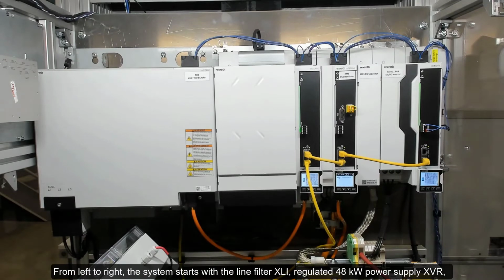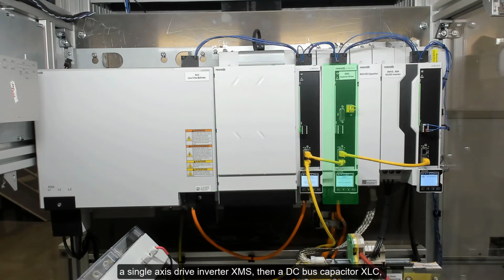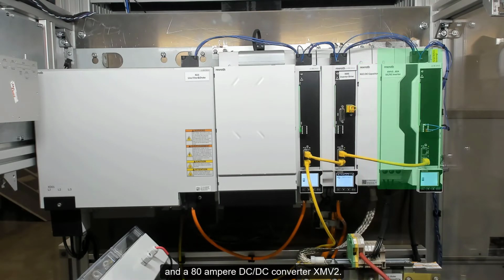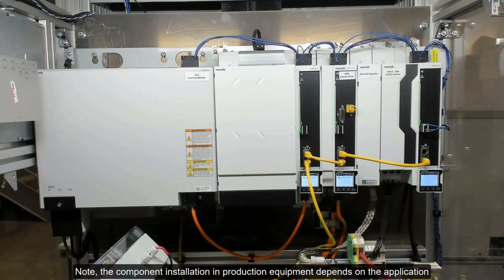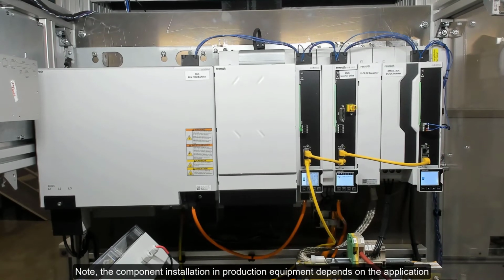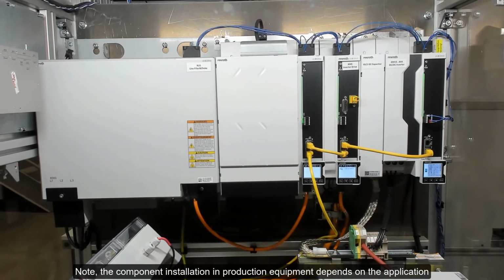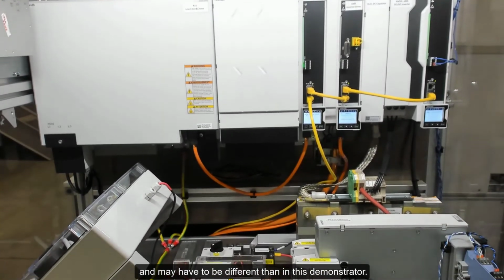From left to right, the system starts with the line filter XLI, regulated 48 kW power supply XVR. A single-axis drive inverter XMS, then a DC bus capacitor XLC. And a 80 ampere DC-DC converter XMV2. Note, the component installation in production equipment depends on the application, and may have to be different than in this demonstrator.